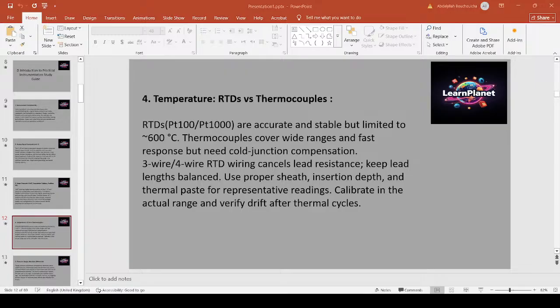Example: for furnace control to 900 degrees Celsius, choose a Type K thermocouple with ceramic insulated extension to the thermocouple transmitter, not an RTD.